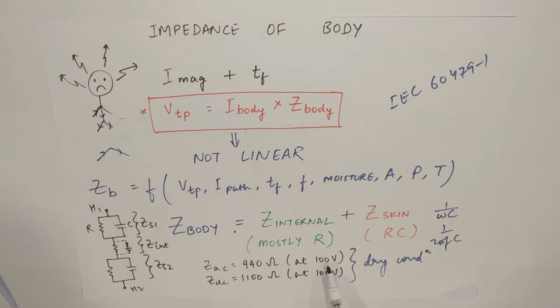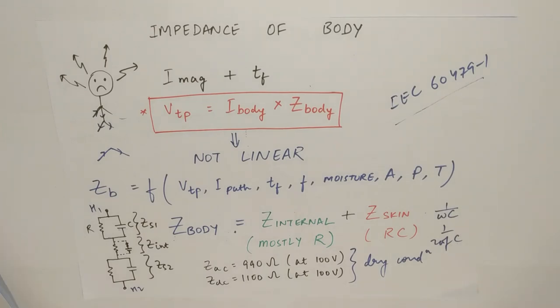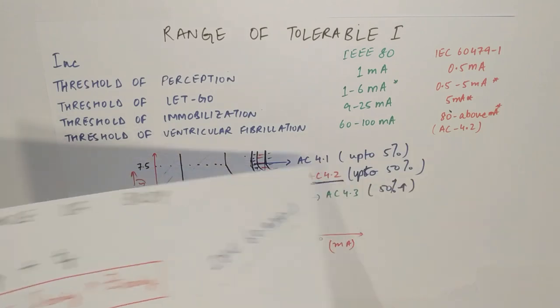Now, I have given an example of 100 volts here. Above 200, both are similar because no effect of skin. At 100 volts, impedance offered by AC is 990. Whereas, in case of DC, it is 1100 ohms. This is in case of dry condition. It depends upon moisture and all. So, I have not taken that example. To refer to other values, you can go back to this IEC 60479-1 and check. Now, we understood the impedance, the nature of impedance, how it works. Now, we understand what is the amount of current that can impact.